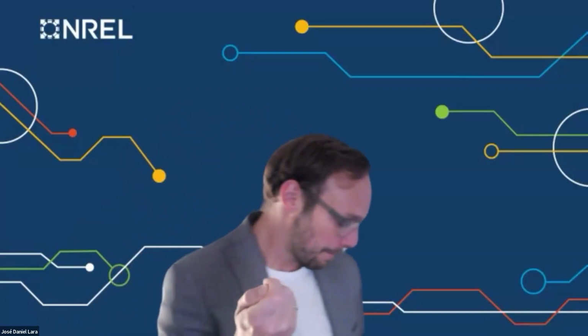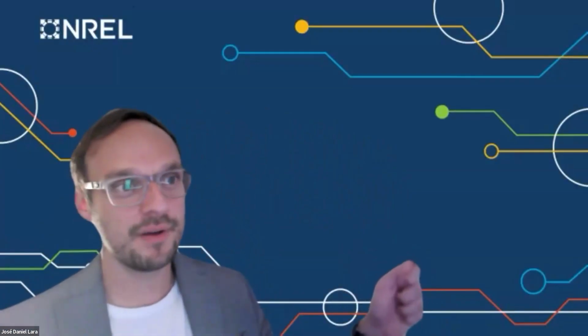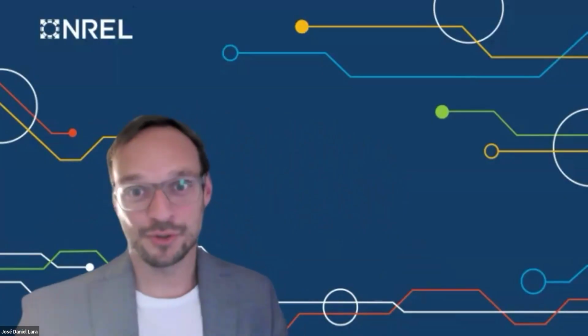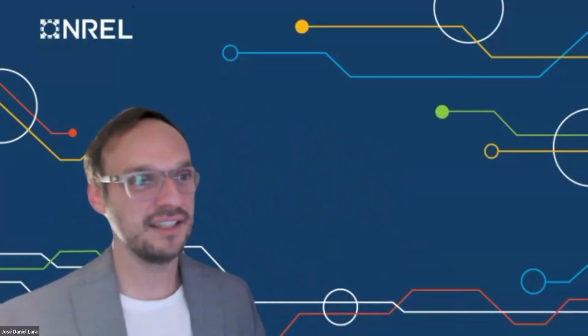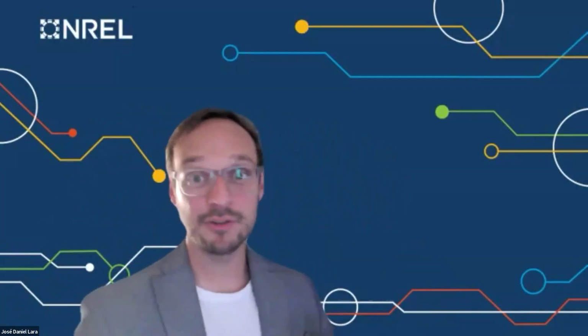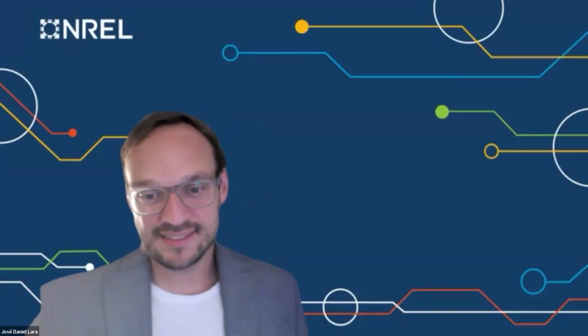To Mustafa's point, this is why one of the yellow blocks of informed opinions was placed on what the operator was doing to control the voltage. In the January case, the report says the nuclear power plant was disconnected from automatic voltage control and was in manual control consuming reactive power, and the under-excitation trip happened when they switched it back from manual to automatic control. There are certain questions we don't know the answers to, but they're definitely important for the conversation.